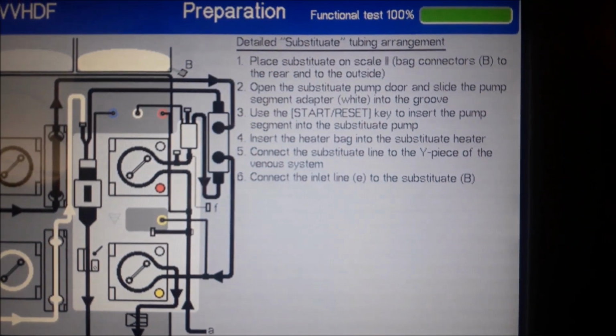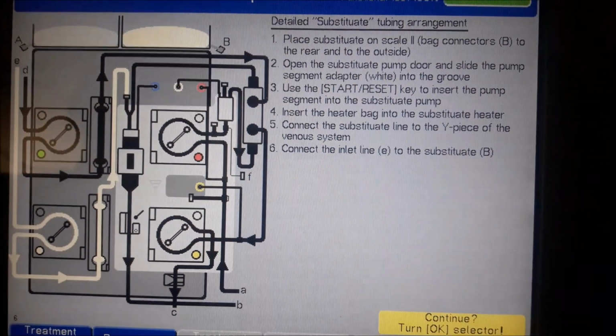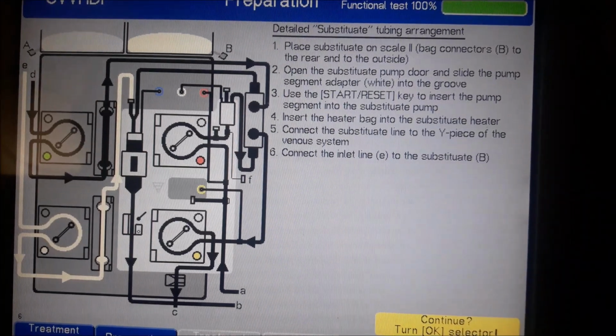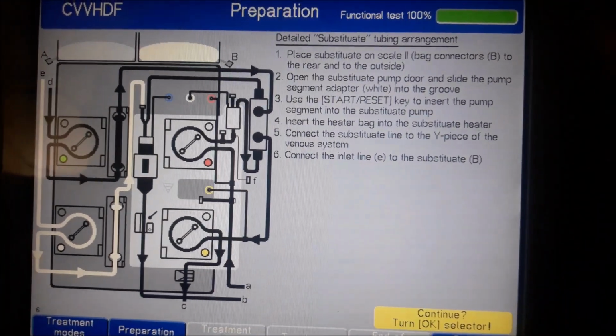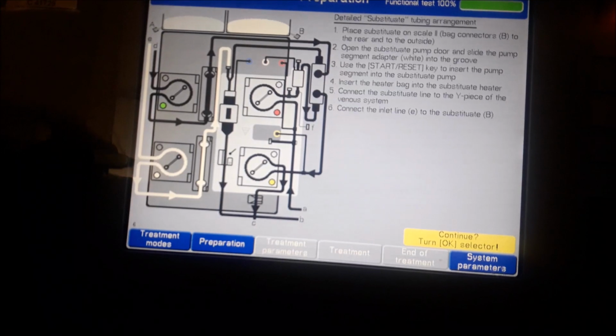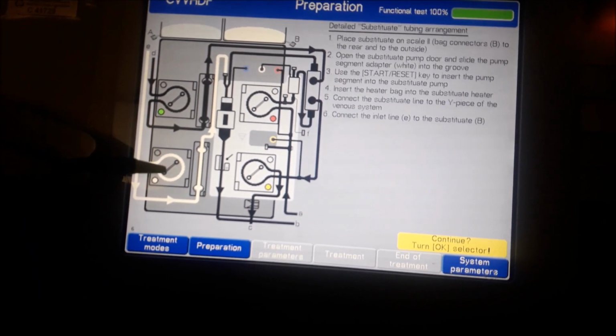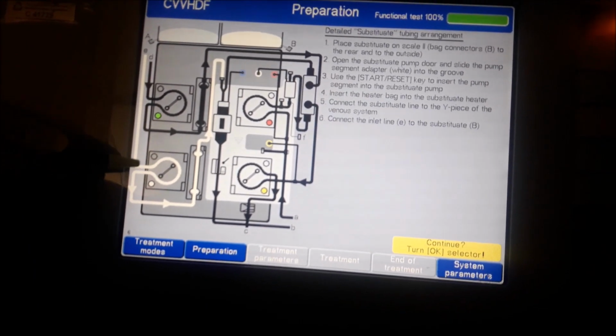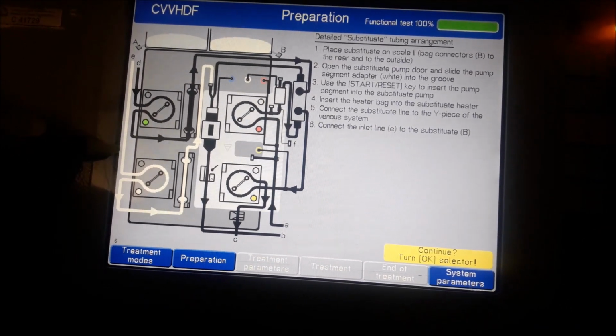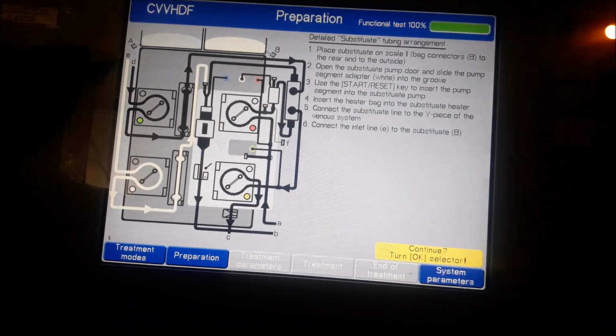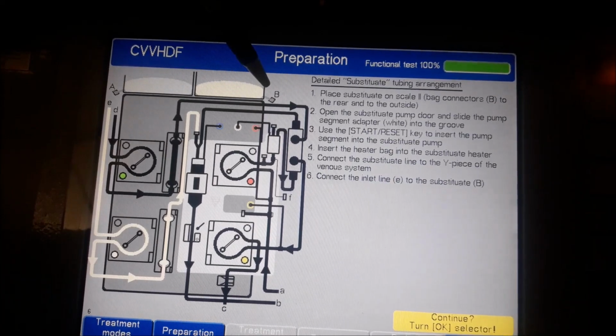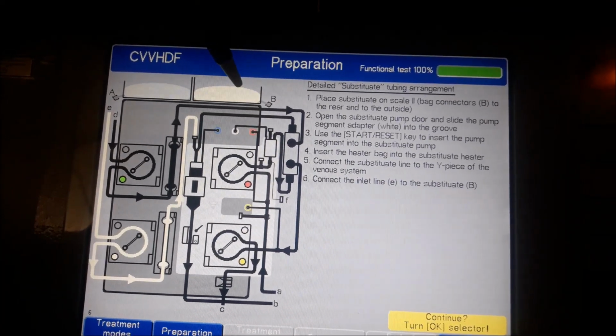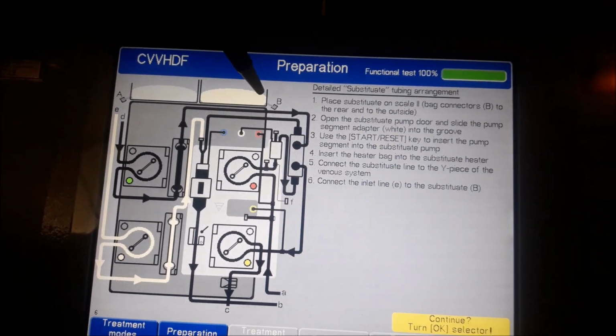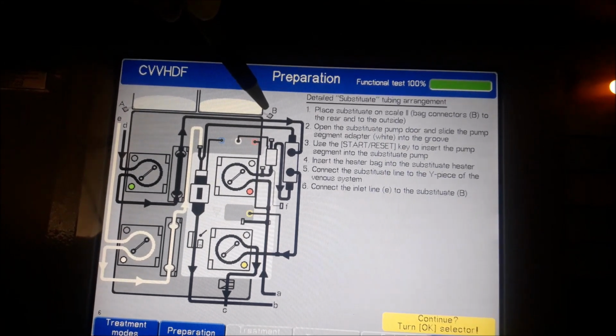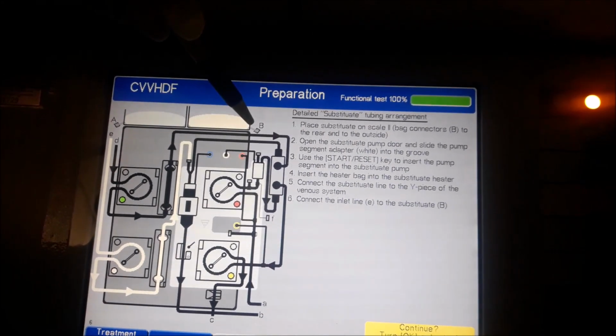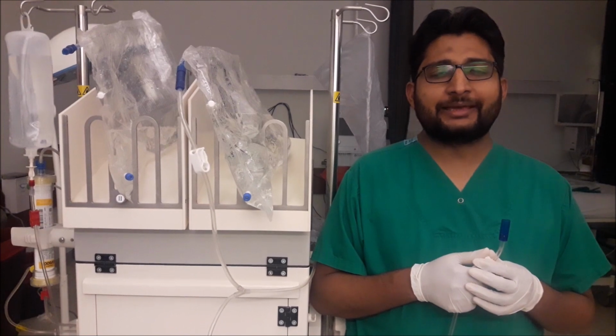Point number 6 is connect the inlet line E to the substitute B. Let's review E and B on the image. Here you can see the white color coated tubing is indicated as the substitute line. Here is the E point. B point is actually scale 2 on which we place our substitute fluid, and B is the external port of the substitute fluid. Now I am again at the back side of the machine.